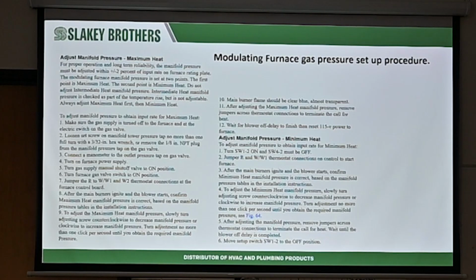And I'll shorten it for you guys because it's a lot of stuff to read here. Simply, you're going to disconnect the communication line. You're not going to use your Connex controller at this point. They're going to have you use just regular jumper wires because you're going to turn this thing into a two-stage. So first thing you're going to do is set the high gas fire rate. So you turn on the unit, you call for first stage, second stage heat with regular jumper wires on the thermostat, and you set your 3.3, 3.4, 3.5, whatever is needed for your area.